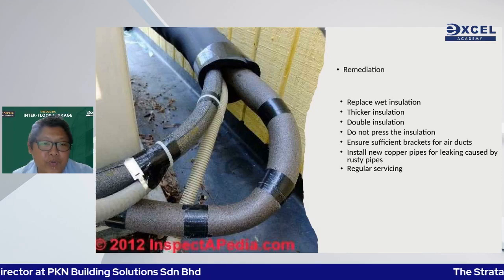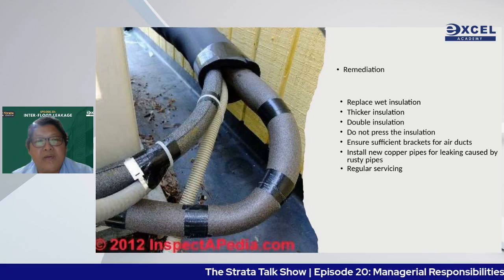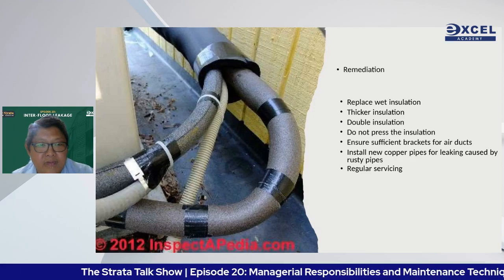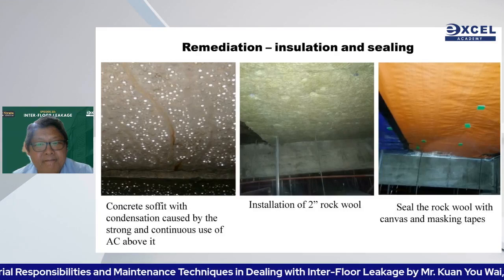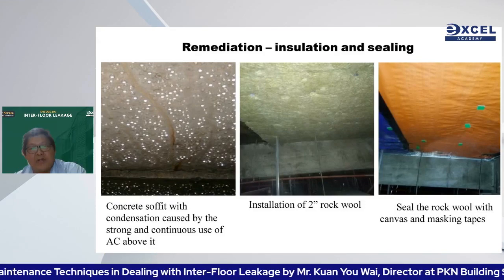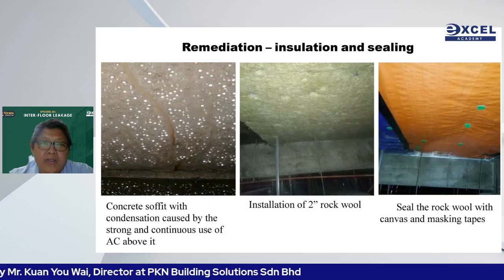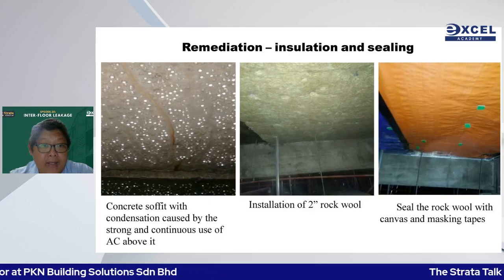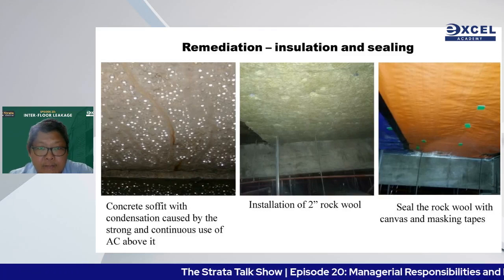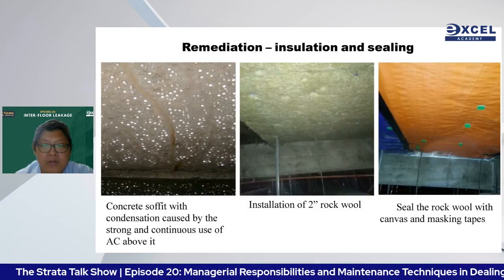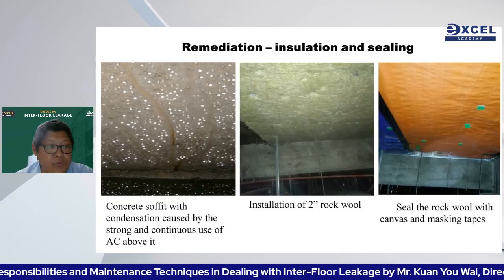Proper aircon insulation should not press out the air. In a server room, rectification was done by installing rock wool and airtight canvas, preventing humid air from contacting cold surfaces above. This method has worked perfectly to date. Only insulation can effectively handle condensation.